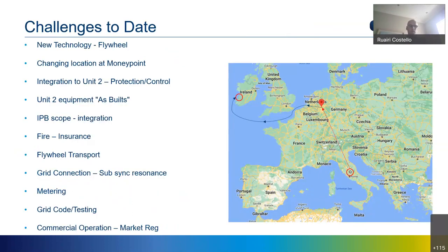So some of the challenges to date: I mentioned the new technology and our internal due diligence on that. I mentioned the change in the site. The integration itself was quite novel to Unit 2 in terms of protection and control. As a result, we had to find documentation belonging to Unit 2, which was over 40 years old, and that was challenging. The IPB scope itself: we had initially decided to change Unit 2's IPB because we couldn't find short circuit information or as-built information on the IPB. So we had to do a study eventually, and we've reduced that scope, which has helped reduce the outage on Unit 2.